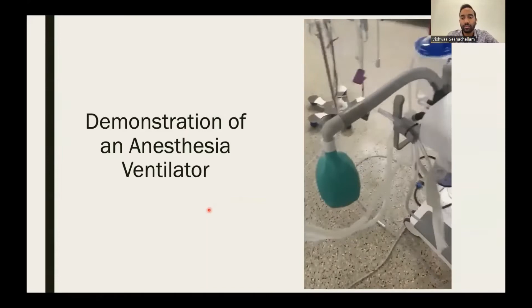Okay. Can you hear? We can hear it. So this machine we have here is a Draeger Perseus A500. I just wanted to show you a pressure control mode of ventilation versus a volume control mode of ventilation. I have made an artificial lung here, just using one of our bags that's usually on the anesthesia machine. Excuse my artificial lung. So what I'll show here is we have a flow, and just keep in mind this is artificial, so our numbers may not match up with what we see clinically.